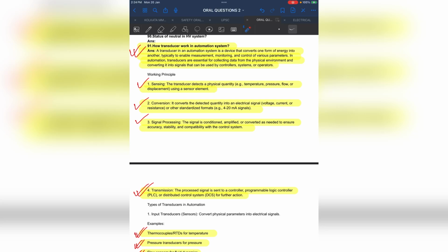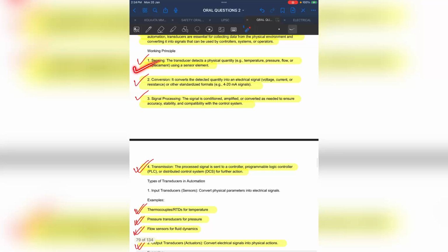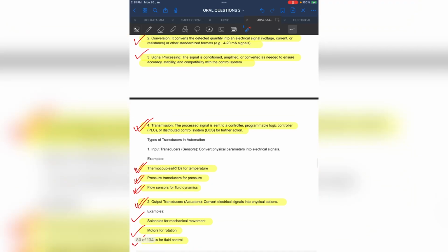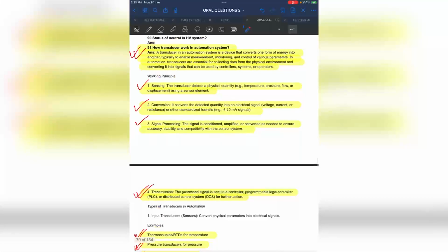So how does a transducer work in an automation system? First is sensing, after that conversion, then signal processing, and then transmission. These are basically the functions. For sensing, the transducer detects a physical quantity. It senses temperature, pressure, flow, displacement using a sensor element. The sensor senses these and then converts the physical parameter into an electrical signal in voltage form or current form.